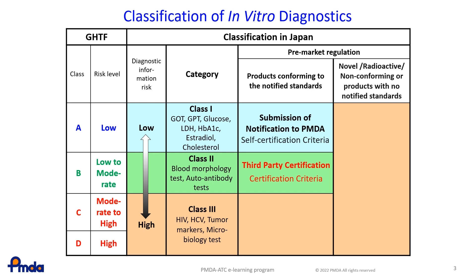Note that products whose specifications do not conform to the requirements, or those that are not substantially equivalent to existing IVDs, or those that are radioactive, need a review by the PMDA and approval by MHLW.